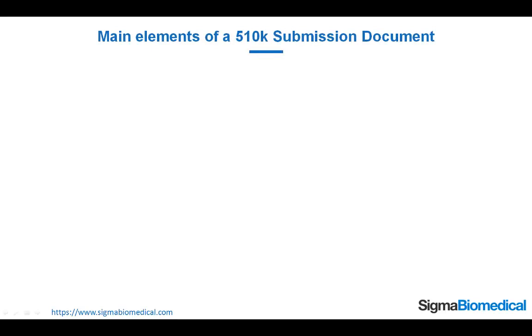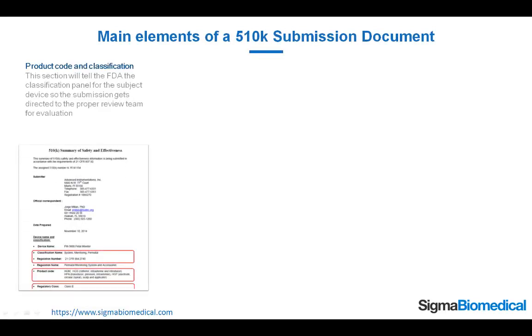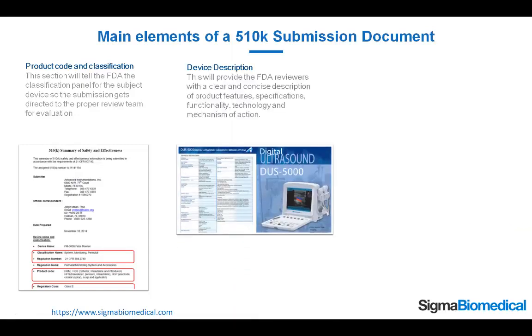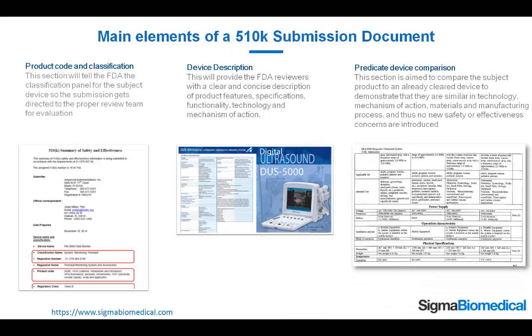Main elements of a 510k submission document. Product Code and Classification: this section will tell the FDA the classification panel for the subject device so the submission gets directed to the proper review team for evaluation. Device Description: this will provide the FDA reviewers with a clear and concise description of product features, specifications, functionality, technology, and mechanism of action. Predicate Device Comparison: this section is aimed to compare the subject product to an already cleared device to demonstrate that they are similar in technology, mechanism of action, materials, and manufacturing process, and thus no new safety or effectiveness concerns are introduced.